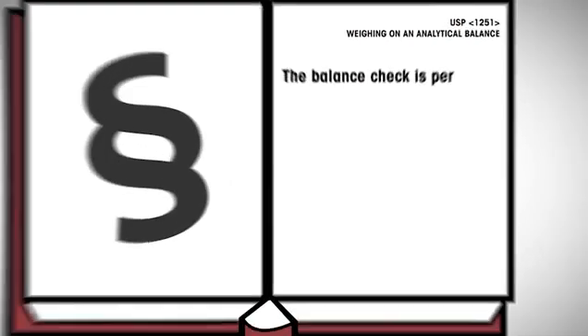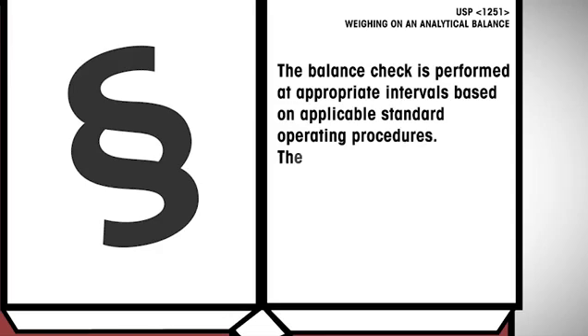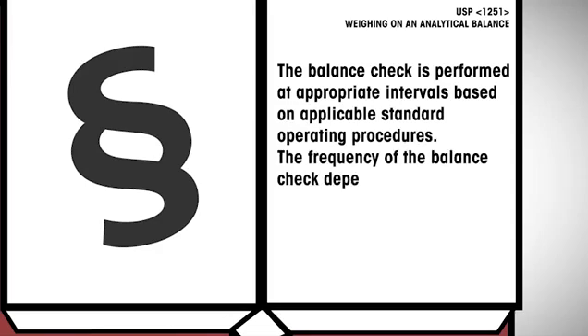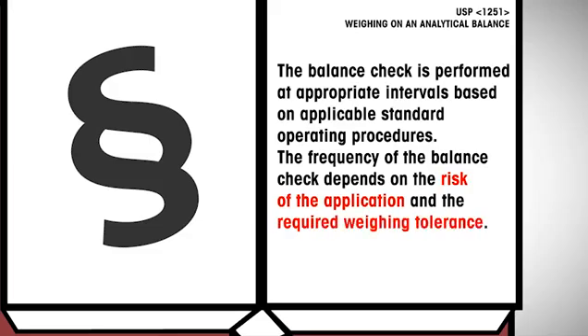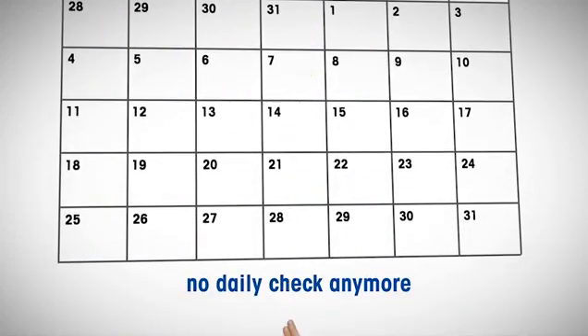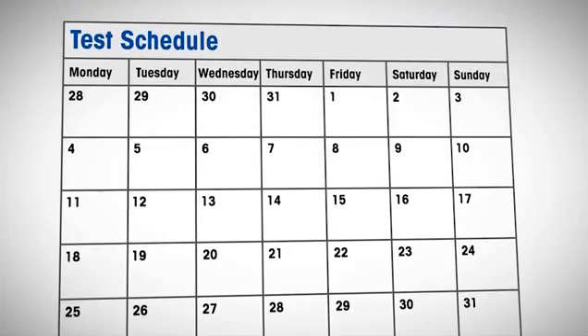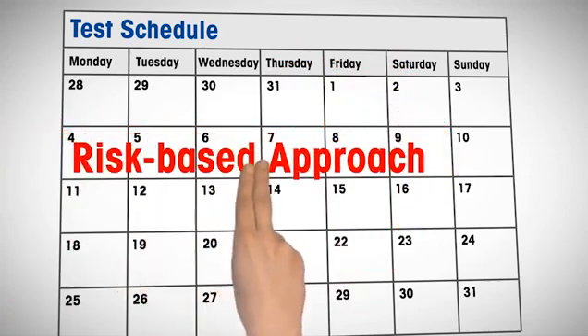The balance check is performed at appropriate intervals, based on applicable standard operating procedures. The frequency of the balance check depends on the risk of the application and the required weighing tolerance. Note that the new regulation does not mention a daily check anymore, as it was the case in the old Chapter 1251. Reflecting current good manufacturing practices, the new USP regulation now recommends a risk-based approach to determine appropriate frequencies of testing.